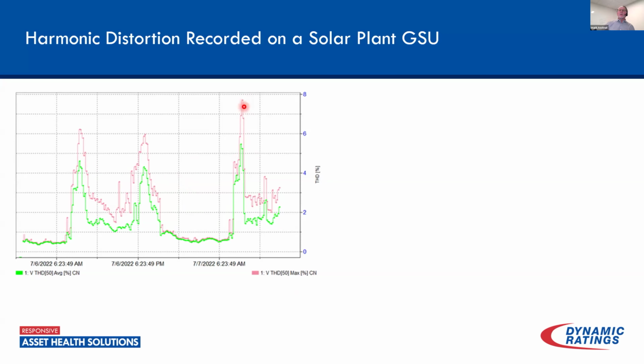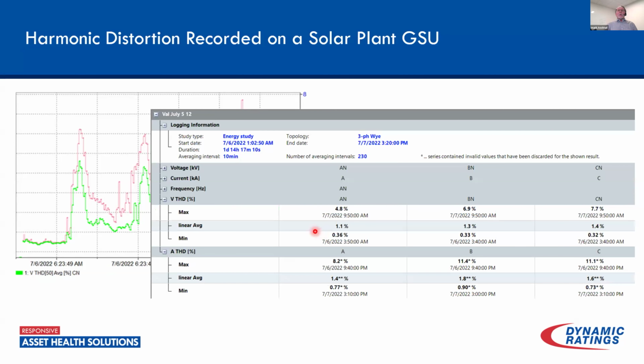But when we start looking at the 3-minute averages, or 3-minute max values, we see our harmonic distortion increases quite a bit. We're approaching values of about 8%. Now, what's really interesting is that just happened to be one snapshot on the waveforms. But I looked through the history, and this power quality monitor happened to be installed for about 3 days. So I looked over the entire duration, and we could see here we're hitting maximum voltage distortions of about 7, approaching 8%. The current distortion is what I thought was really interesting: 11.5, 11.4. So we're exceeding 11% total harmonic distortion when it comes to the current. And again, those IEC and IEEE limits are about 5%.